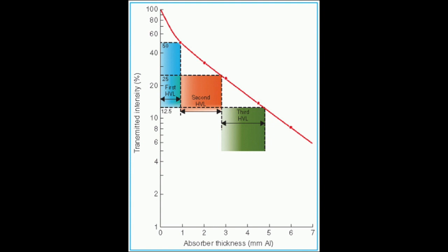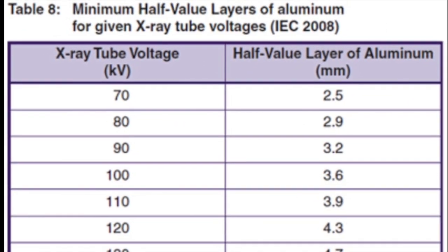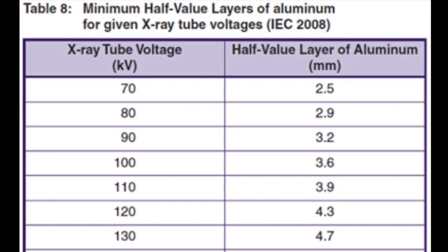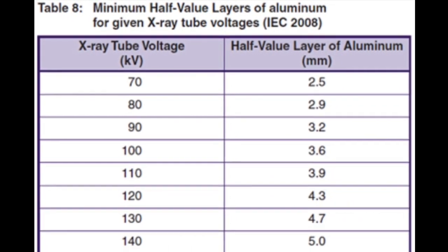Generally, when the HVL value reduces, it is a result of less kV being applied to the tube. An increase, assuming that the applied kV value is accurate, may be evidence of extraneous reactions with particles in the tube, which may occur as a result of tube aging. The following chart represents half-value layers for specific kVp values.